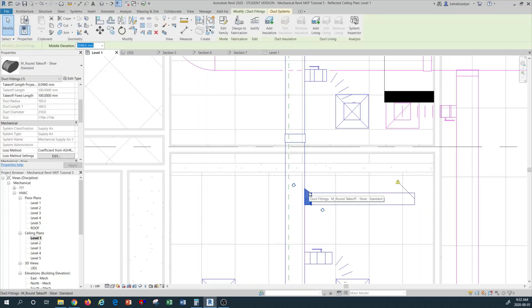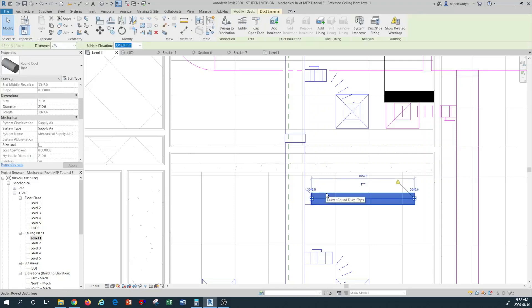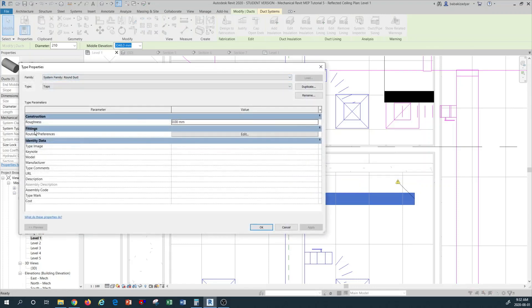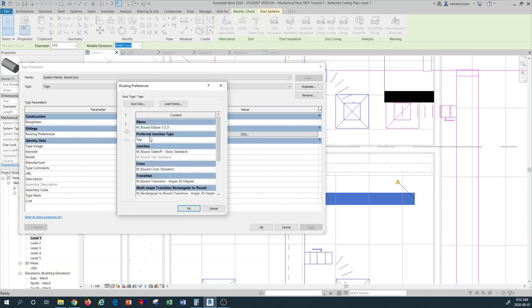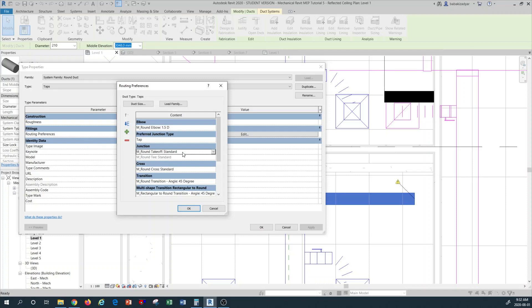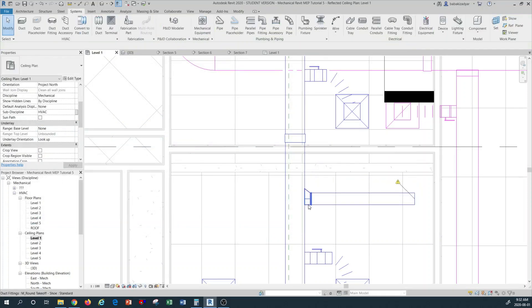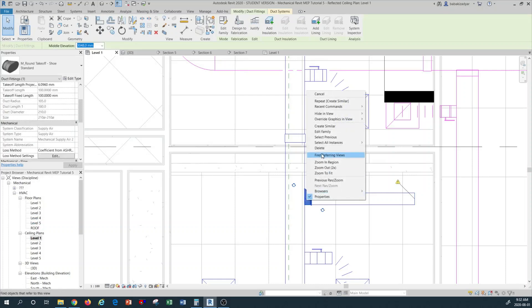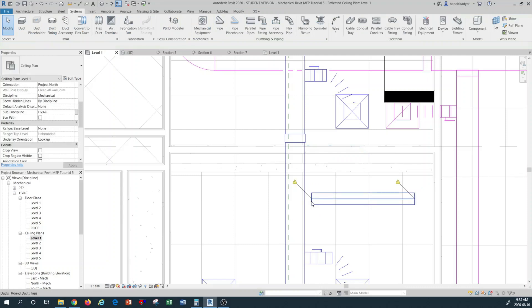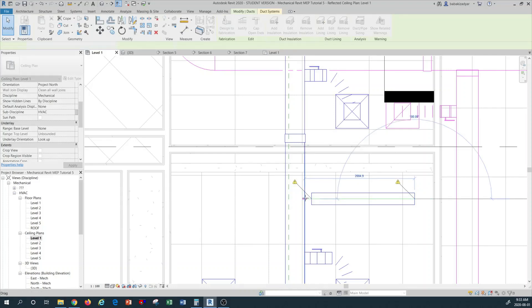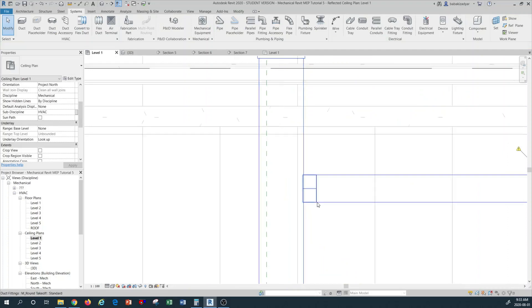By left clicking on your ductwork, you come to Edit Type for your duct. By pressing Edit Type, the fitting routing preferences is where you need to work. Press Edit there. The junction type is set to tap — leave that. In here, normally I've changed it to standard type so you can see how it changes. Select that, apply, and OK. Now if I delete this connection duct and grab it again to connect to this duct, you see I have a regular standard connection.